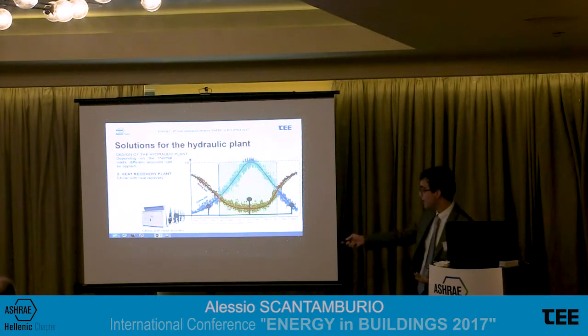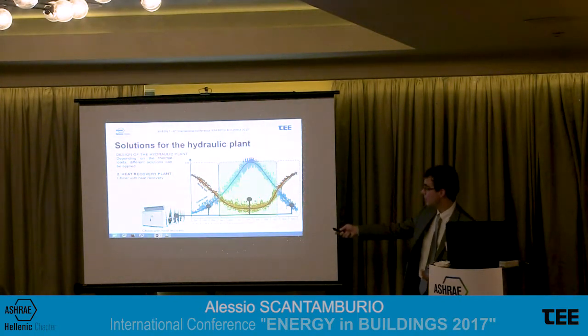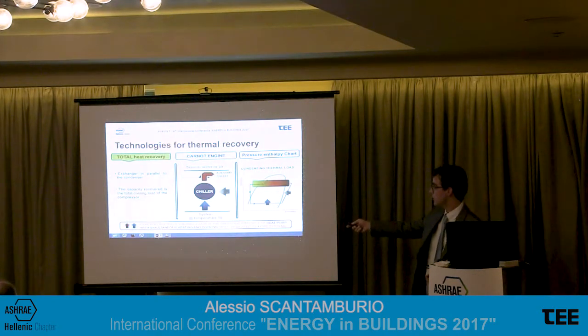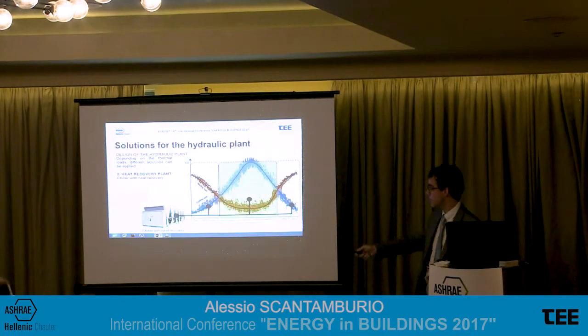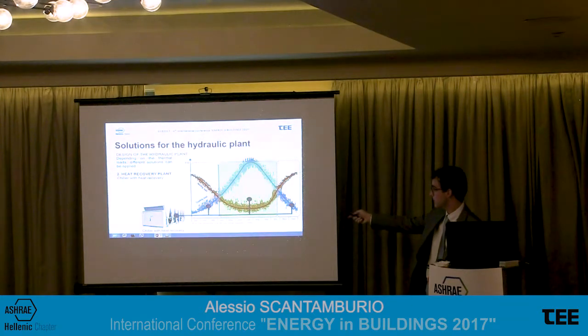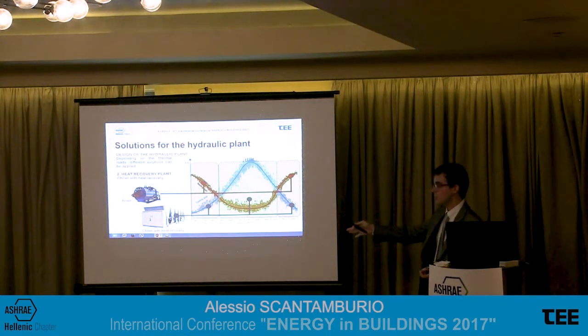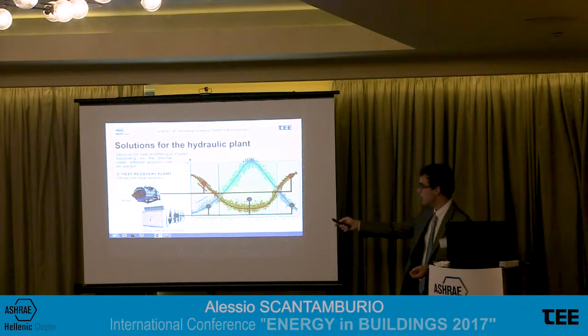So, okay, for all the part where the cooling load is higher than or at least equal to the heating load, with this technology we are able to recover at least the maximum cooling load of the compressor. We are not able to fulfill these particular areas here. So even with the chiller with heat recovery, we still need a boiler. We still need an additional system to provide the heating when the heating load is higher than the cooling load.